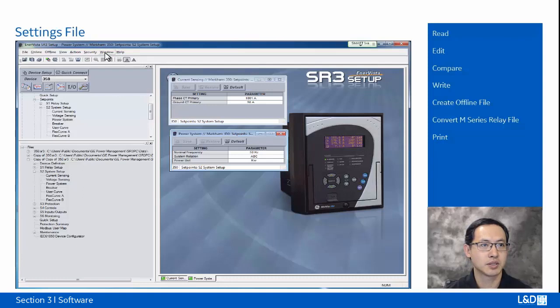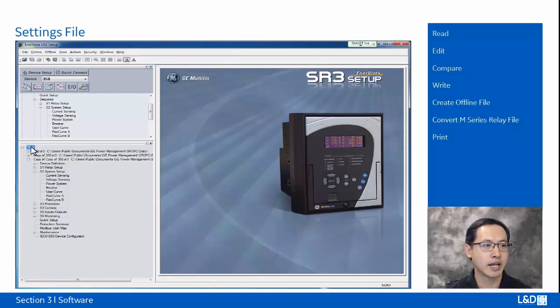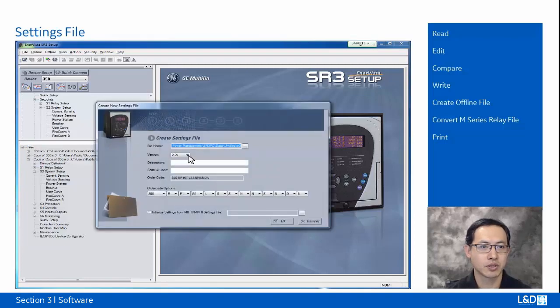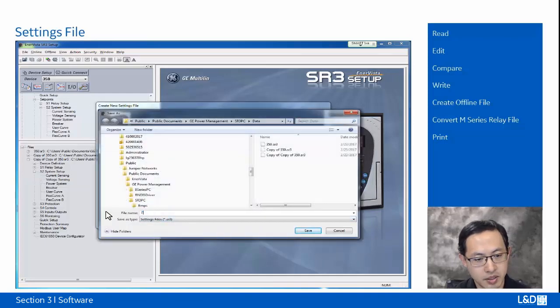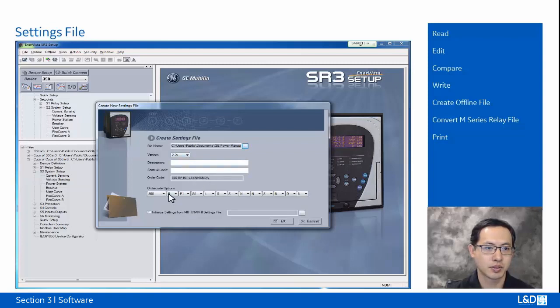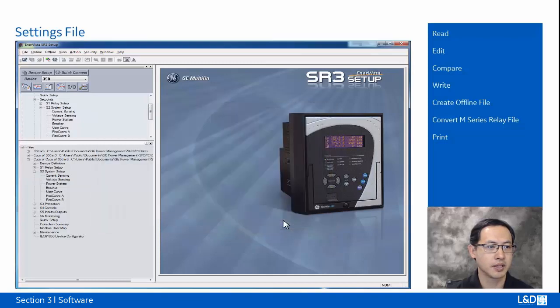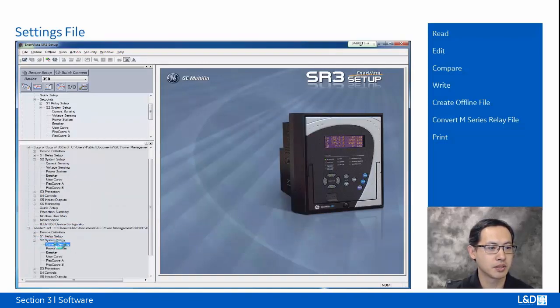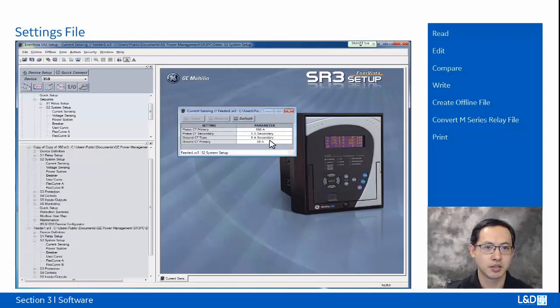Another thing we can do with setting files is create a new setting file in the offline area without having any relay. So right-click the mouse and choose new setting file. From new setting file, we can give a name and we can choose the version number. We can select the order code. So for example, I'm going to choose this relay called feeder 1 again, give a version number 2.2, select a different order code and click OK. Now this feeder 2 relay is created, and because I picked a P0, that's a universal CT, I can see the CT options for the secondary, 1 amp or 5 amps.